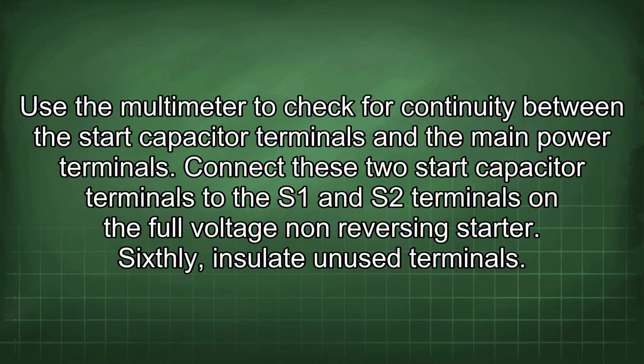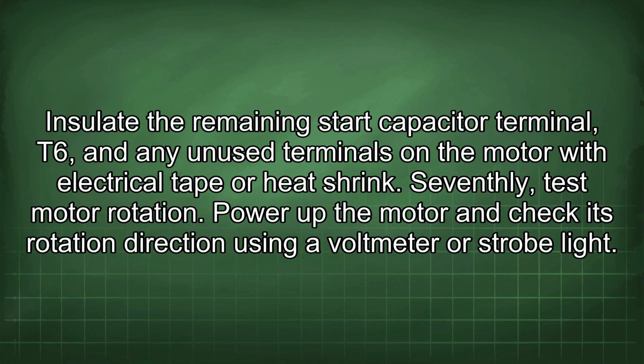Use the multimeter to check for continuity between the start capacitor terminals and the main power terminals. Connect these 2 start capacitor terminals to the S1 and S2 terminals on the full voltage non-reversing starter. Sixthly, insulate unused terminals. Insulate the remaining start capacitor terminal, T6, and any unused terminals on the motor with electrical tape or heat shrink. Seventhly, test motor rotation.